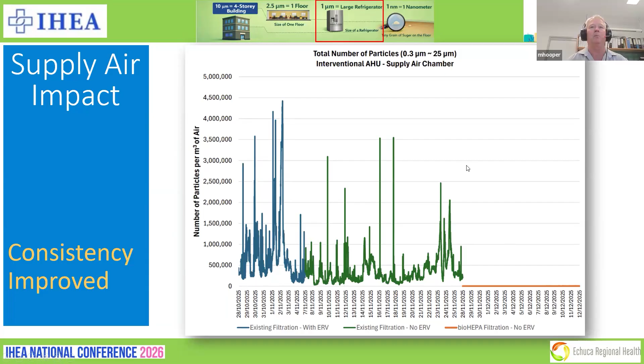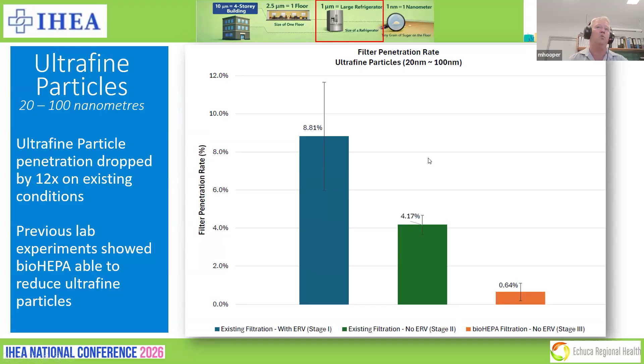Now if we look at ultrafine particles, which is 20 nanometres to 100 nanometres - so now we're starting to get down to grains of sugar up to the size of Coke cans, stuff that's nanometres, not micrometres. With our existing filtration, we were still getting 8.8% of these particles passing through our F9, so the F9s were doing pretty well. But on our bioHEPA, we were getting 0.64%, so a 12 times reduction compared to between our study unit and our normal unit.